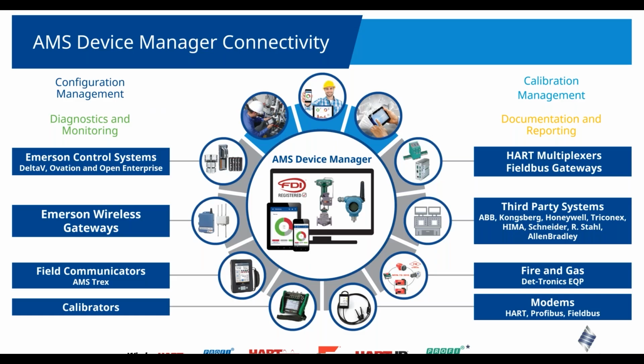AMS Device Manager is software on top, and there's no action if you cannot get to the bottom. So AMS Device Manager connects to all open protocols: HART, Foundation Field Bus, Wireless HART, Profibus, and soon Profinet with the help of Softing. But from the bottom layer, from the field, to the top where Device Manager sits, you need some kind of communication path. You already have the wiring and all that good thing in, but sometimes we don't understand the language or the protocols, because there are lots of manufacturers out there that use proprietary protocols.